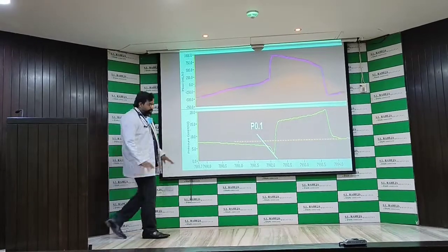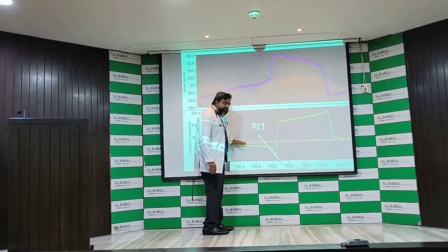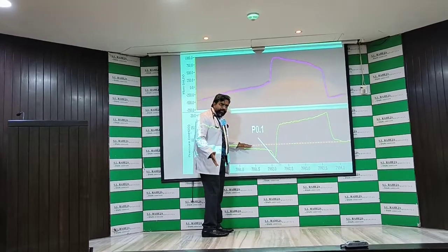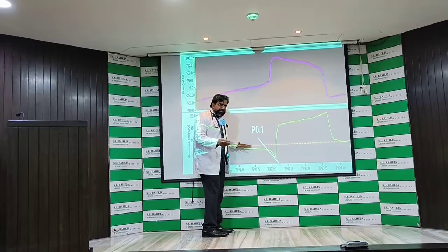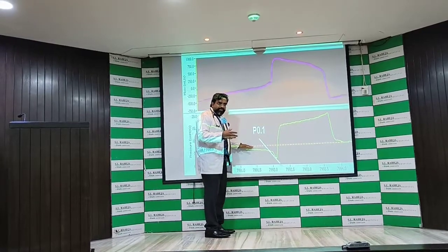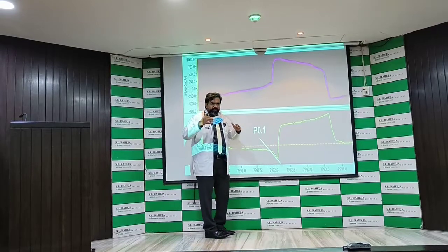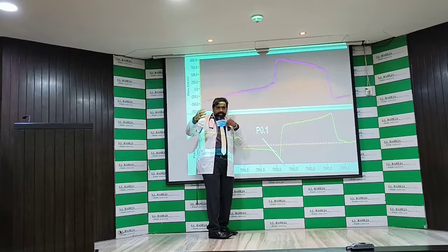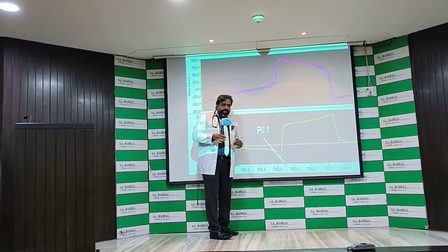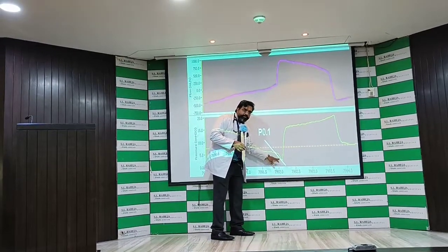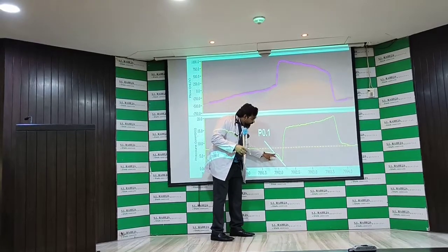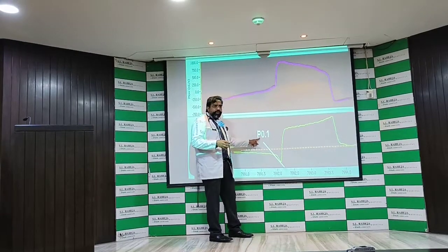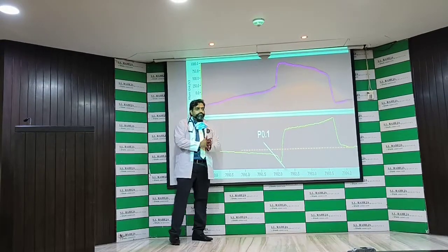Okay? I'll explain. At this moment, there is no breath happening. The airway is occluded. There is nothing happening here. It is just stopped. Just when the patient is taking a breath, the ventilator valve has to open when the patient triggers, so that air can be taken inside. What the ventilator importantly does is it actually sees this drop before the valve opens and calculates the slope. This slope at 100 milliseconds is called P0.1, which actually gives you inspiratory effort.